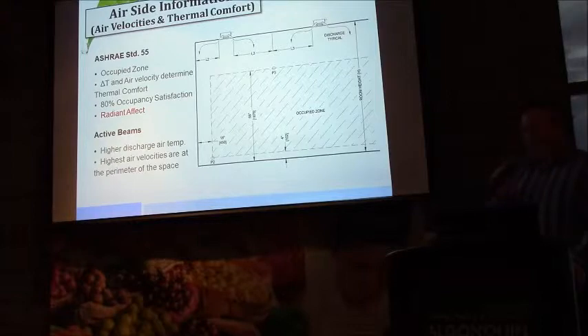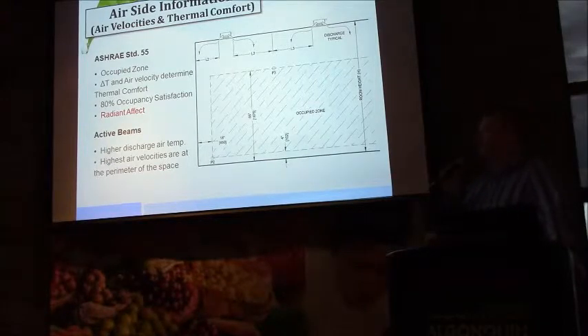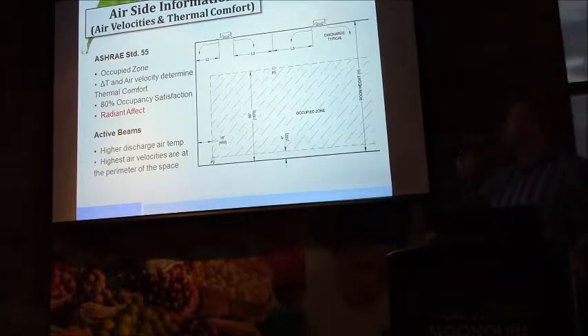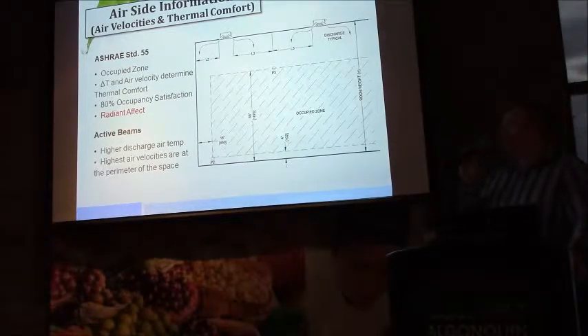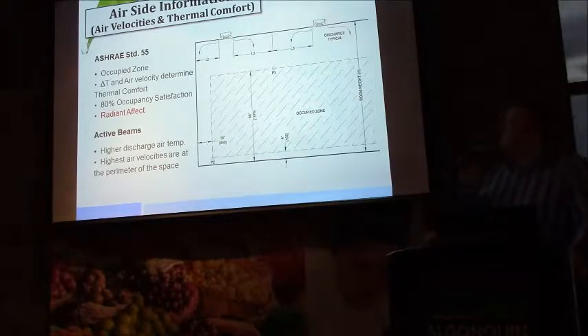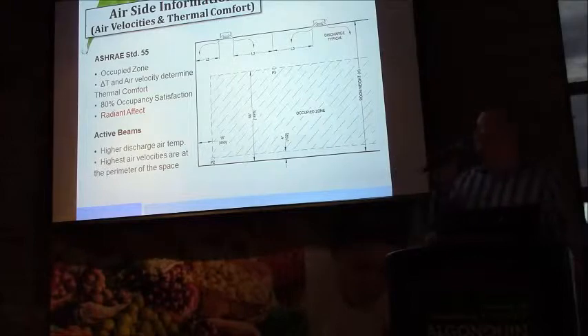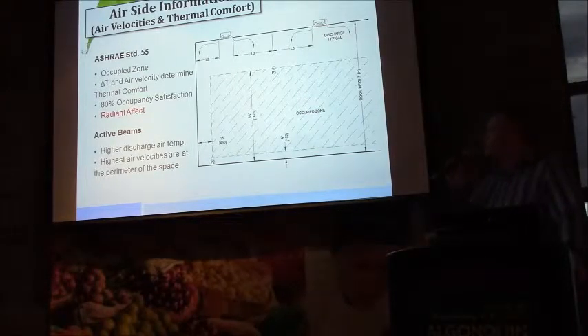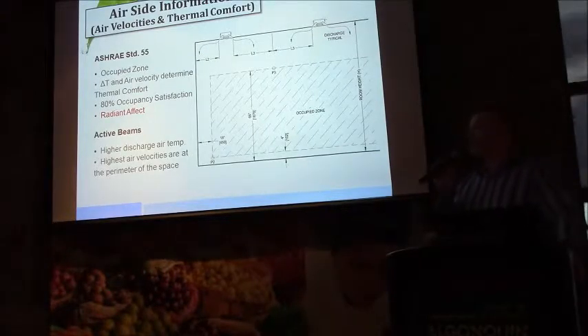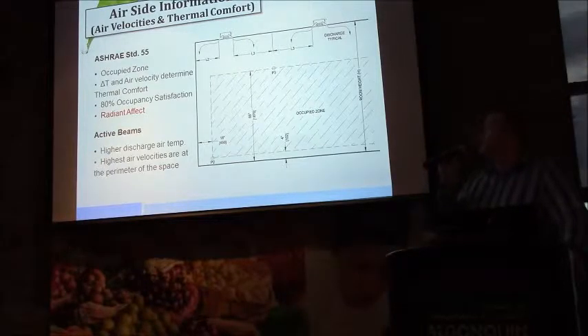So beam placement and orientation within the space becomes the next talking point, because it's not a difficult piece of equipment to install in the space relative to the air distribution. Again, it's treated like a linear slot diffuser. The most critical point obviously becomes P3, where the two colliding air streams combine and can create a draft in the occupied zone. Obviously down here at P2, where the air is discharged down the sidewall, is less of a risk factor, as it's technically outside of the occupied zone by ASHRAE definitions, but still a concern and still something that should be checked.